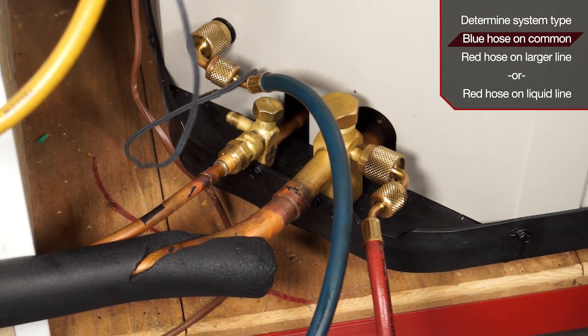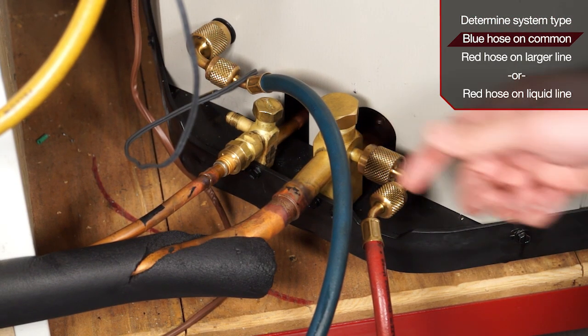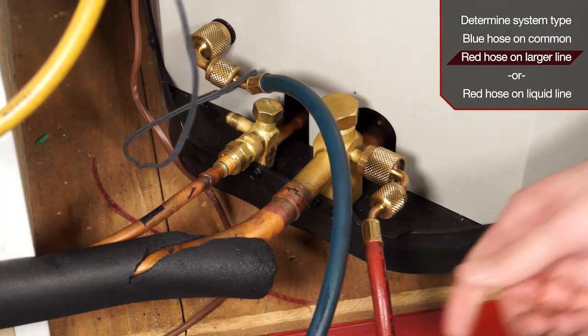When hooking up to a piston driven system in heat mode, you will hook your blue hose to your common suction port and your red hose to your larger copper line.